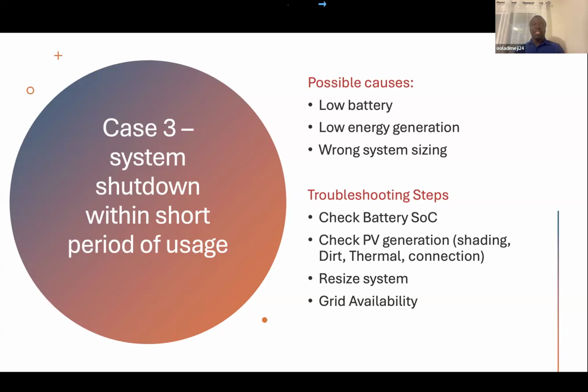If your load has changed, then the system needs to be reevaluated. You need to resize your system. That means your load is changing. Either you let your clients know that the load has changed and they need to maintain the agreed load, or you let your clients know there is need for reevaluation of the system and resizing of the system or an upgrade. So this way you're able to resize based on the load that is connected to the system.